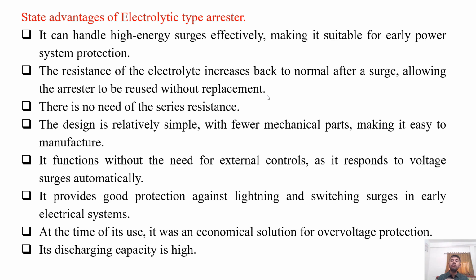The design is relatively simple with fewer mechanical parts, making it easy to manufacture. It functions without the need for external controls as it responds to voltage surges automatically. It provides good protection against lightning and switching surges in early electrical systems. At the time of its use, it was an economical solution for overvoltage protection. Its discharging capacity is high. So, these are several advantages of the electrolytic type arrestor.